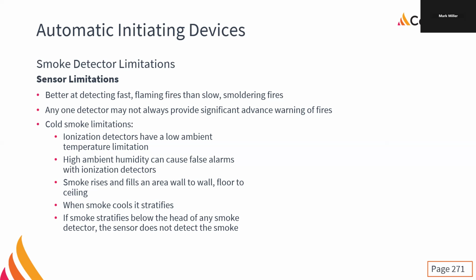We can have issues. Sometimes you think a smoke should have gone off and it hasn't. It might be the next one down, the hallway that picks it up. And it could just be because of the nature of the airflows. Or, that first one was very, very clean. The second one was a little bit on the dirty side, so it was a little bit more sensitive. I mean, it can be a little bit hit and miss.